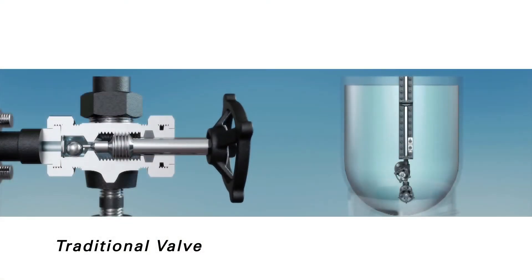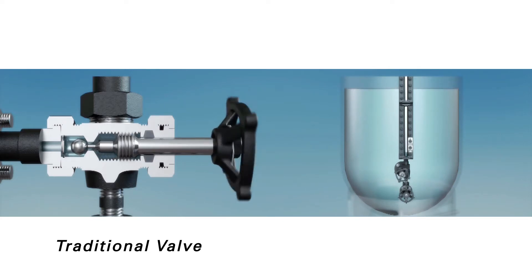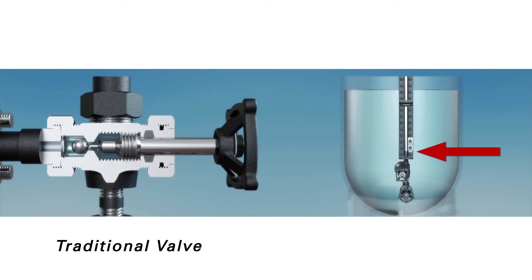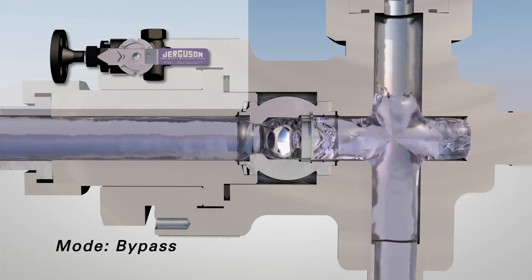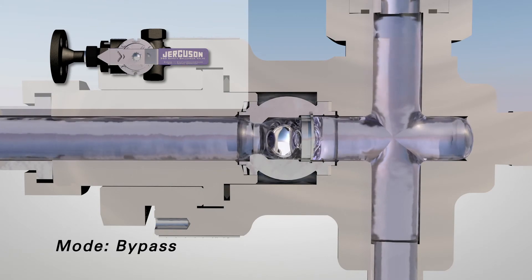When using a traditional ball check valve and commissioning a gauge assembly when there is already liquid present in the vessel, it is common for the user to open the valve too quickly, causing the ball check to engage and the level gauge to display a false level reading. As previously demonstrated, this is eliminated with the new Jerguson 360 ball check valve.